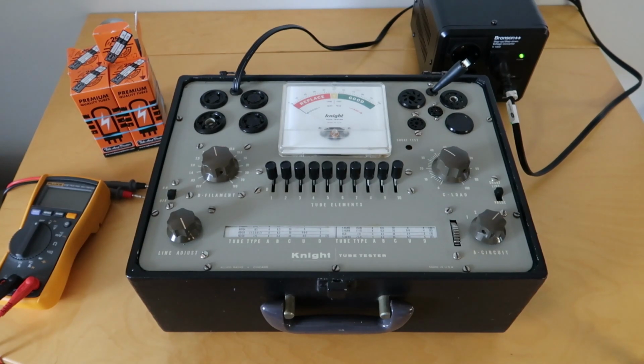What we see here is a Knight 600 valve tester, a unit made probably in the late 1950s or early 1960s in America. It's designed to test valves quite crudely, to check for good or bad, for short circuits at low plate voltages, and for gas, meaning whether the valve is grossly leaking.